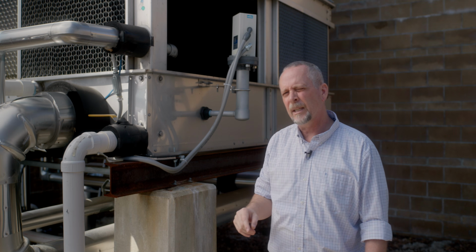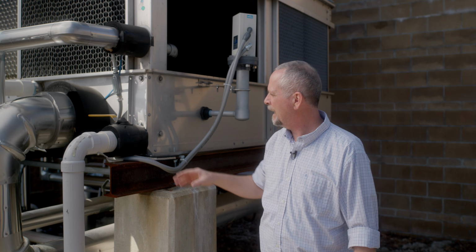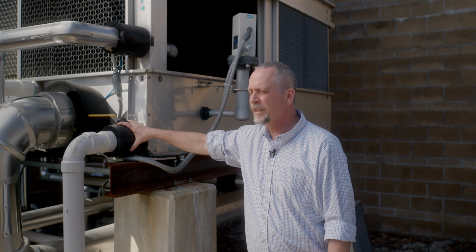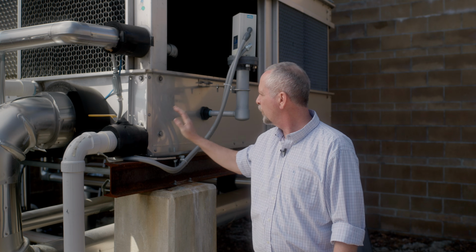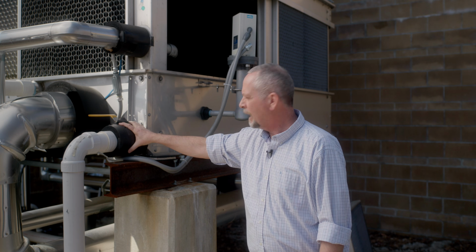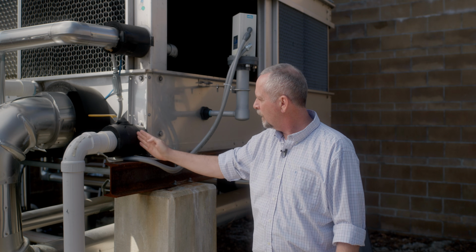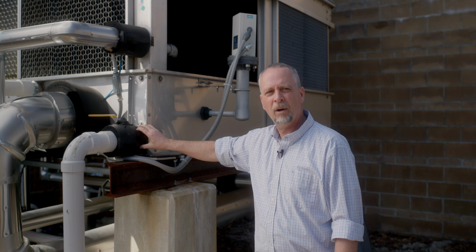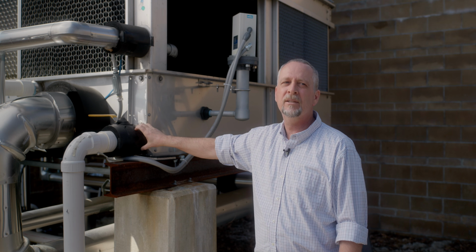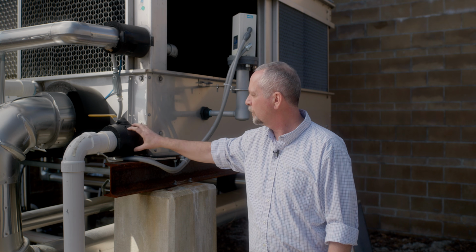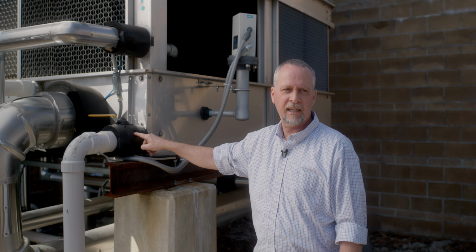One other important one to heat trace, that doesn't get hit all the time, is this brass valve. This is a drain valve. So if I wanted to drain all the water out of this tower, I would open this valve. Therefore, up to the center of this valve, I've got water here. It's a brass valve. These freeze and bust quite a bit too. So another good practice, heat trace that guy as well.